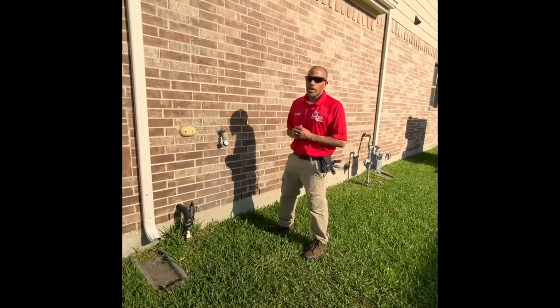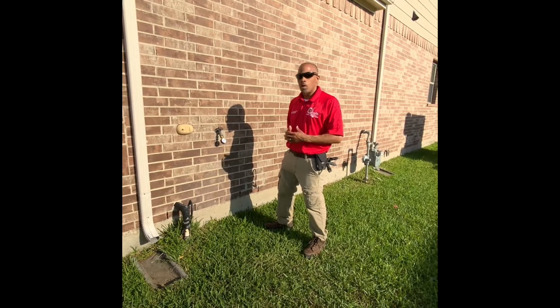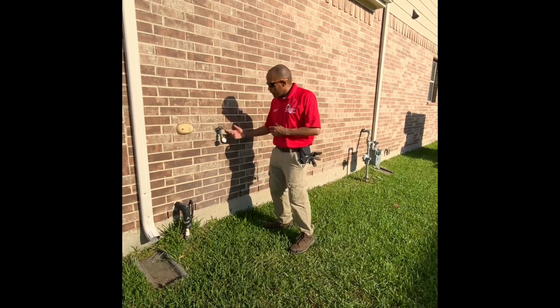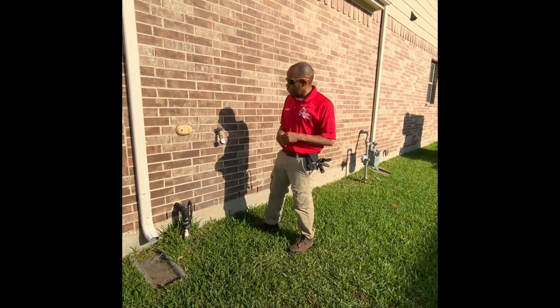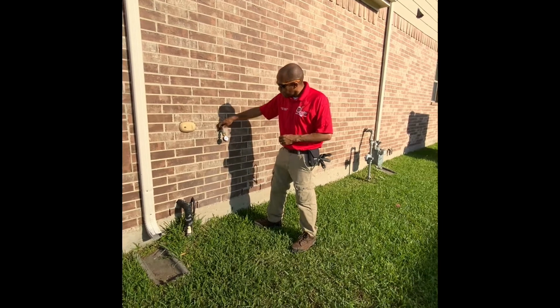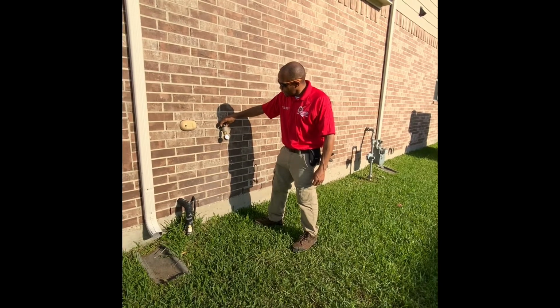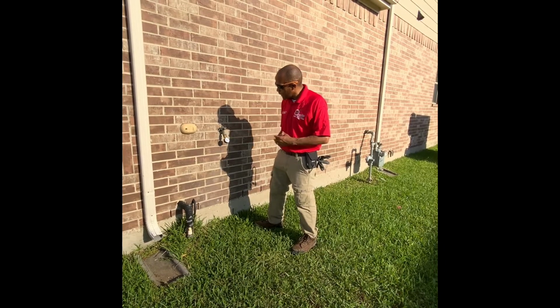We also check your plumbing distribution systems. We check for functional flow. And right here, I'm actually checking the static water pressure of your home. It should be between 40 and 80 PSI. Right here we have about 40 PSI, and there is a little leakage there.